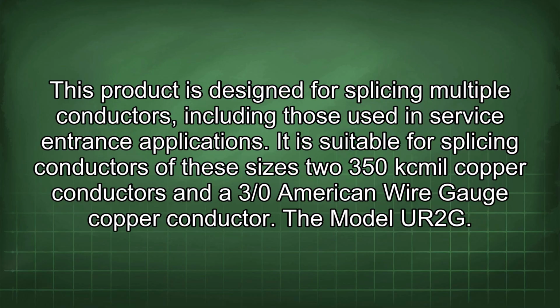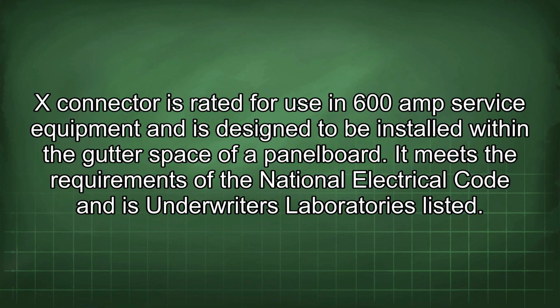It is suitable for splicing conductors of these sizes: two 350 kcmil copper conductors and a 3/0 American wire gauge copper conductor. The model UR2G connector is rated for use in 600 amp service equipment and is designed to be installed within the gutter space of a panel board. It meets the requirements of the National Electrical Code and is UL listed.